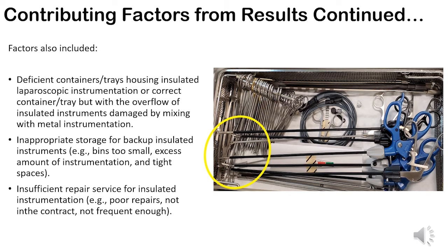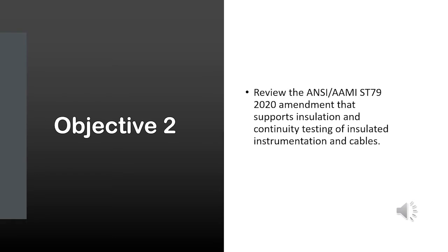There was also an insufficient repair service for insulated devices. For example, they had poor repairs. Maybe it wasn't even in the contract to look at the insulated devices, only the metal instruments that were within the tray. And also, the repairs were not frequent enough. So now let's go into Objective 2 and review the ANSI AAMI ST79 2020 amendment in this new section 8.2.1.